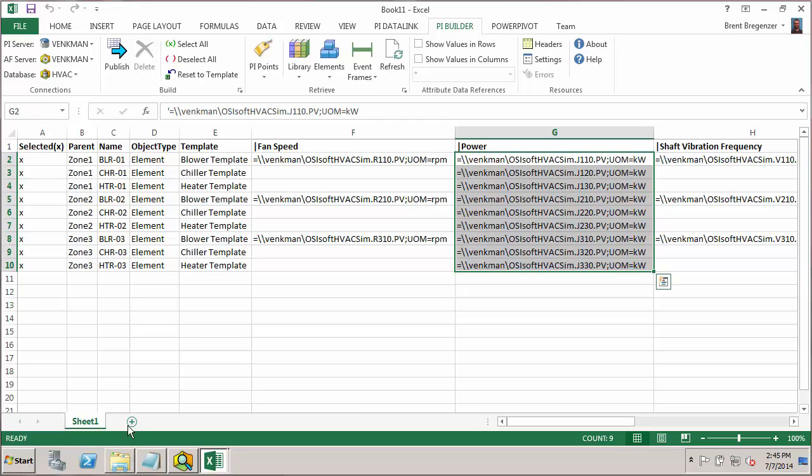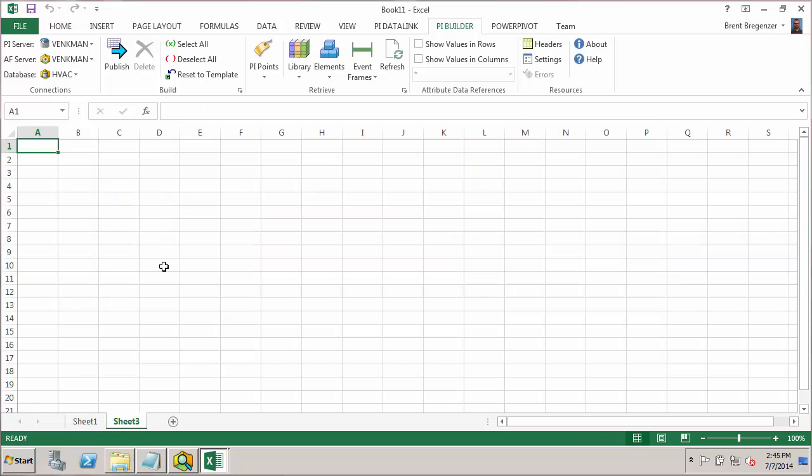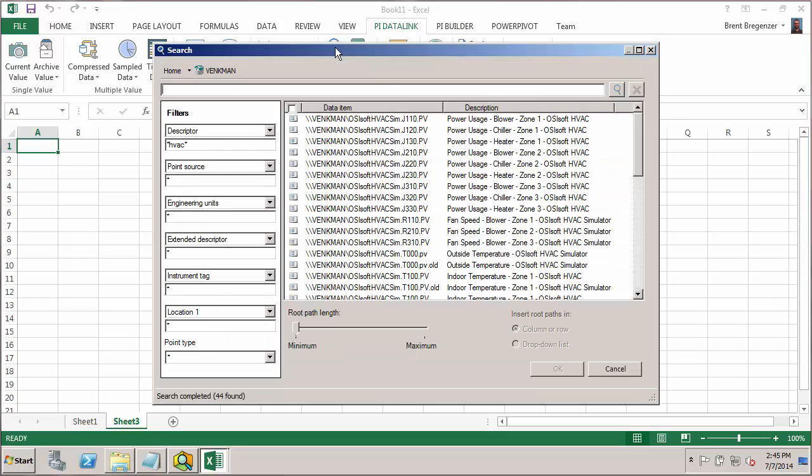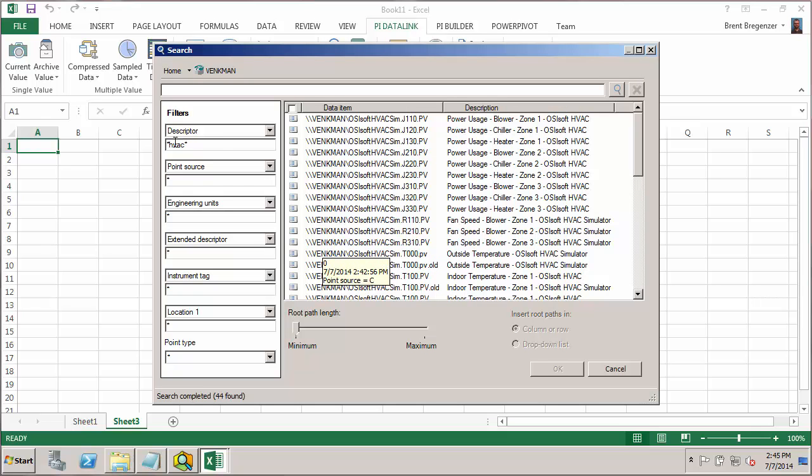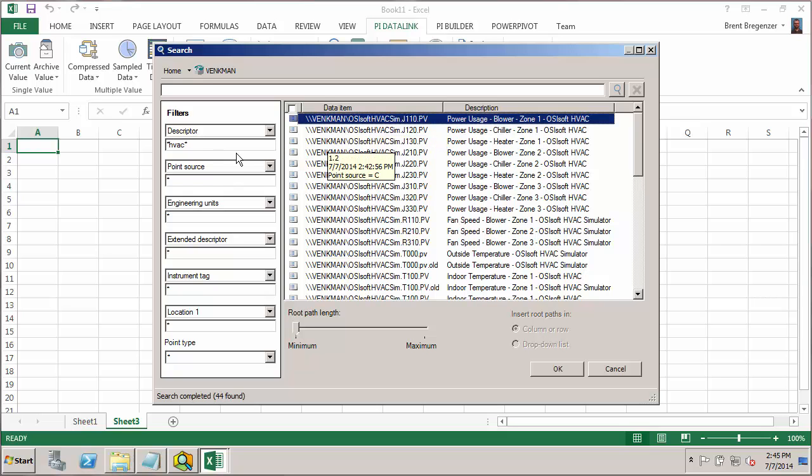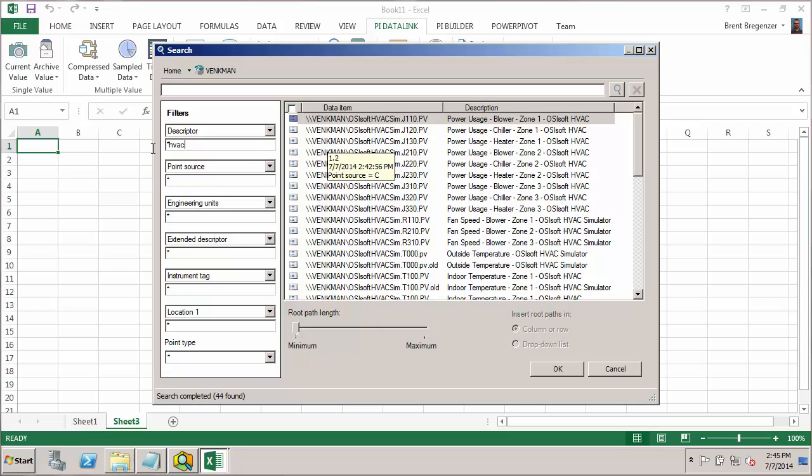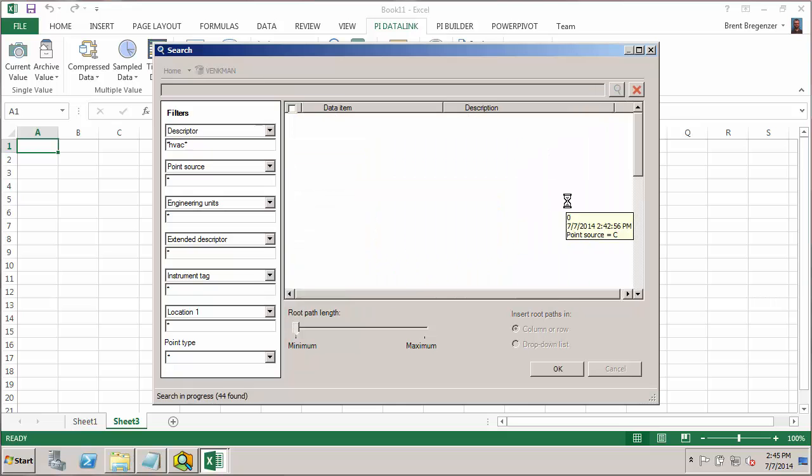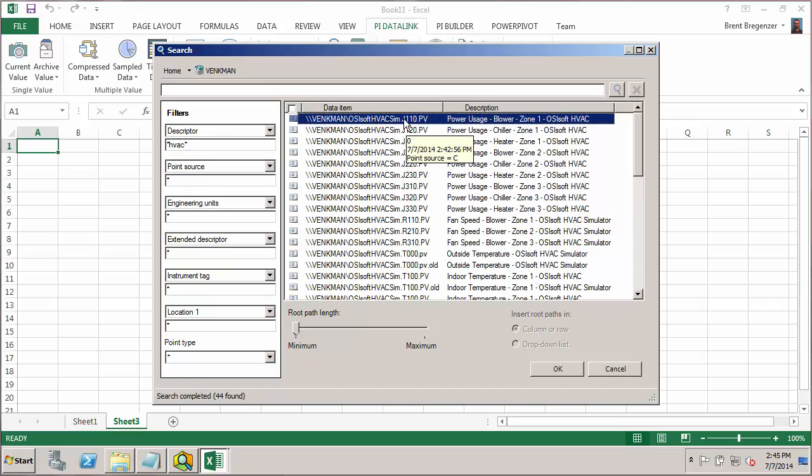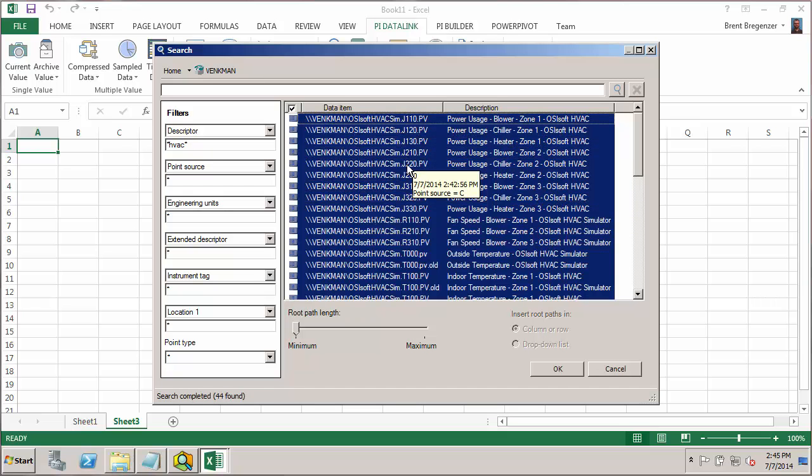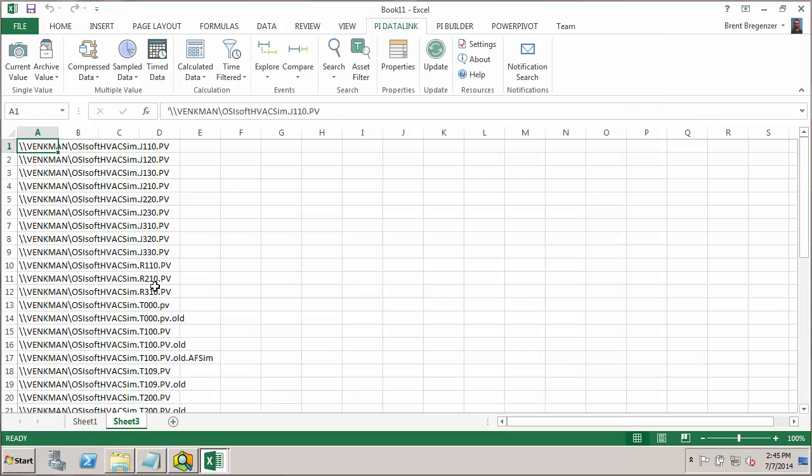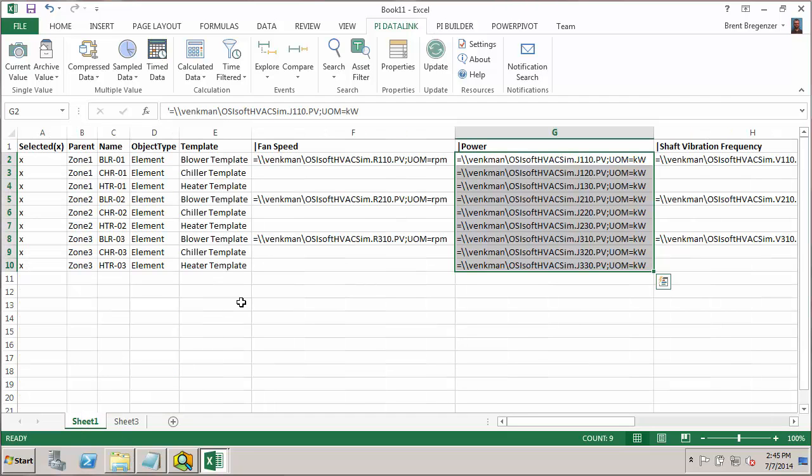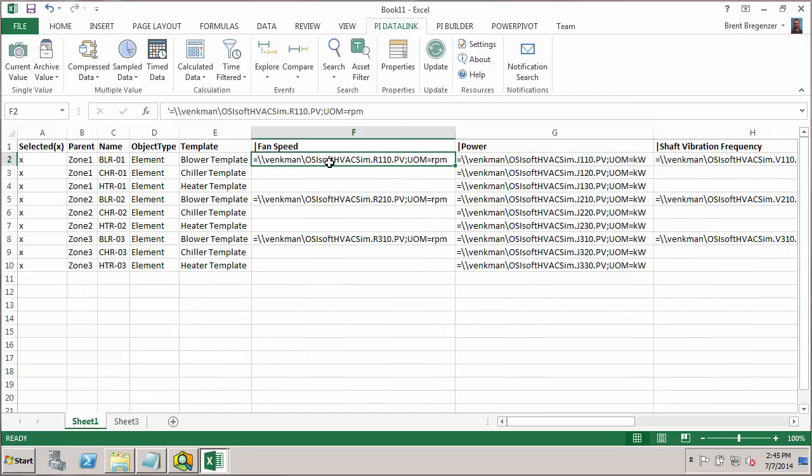And if you wanted a convenient way to get tag names in the right format, if you have PI Datalink, you could just go to the search. And here I've already done a search. I know that all my HVAC tags have HVAC in the descriptor. The way I did that, I just typed star HVAC star. Hit the search. It turns up all my HVAC tags. I could do a control A to grab all those and hit OK. And you can see that they're already in this convenient format with the slash slash server name slash tag name that needs to be used when configuring these configuration strings.